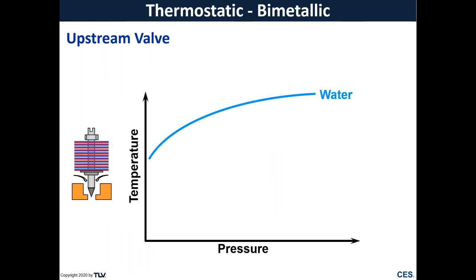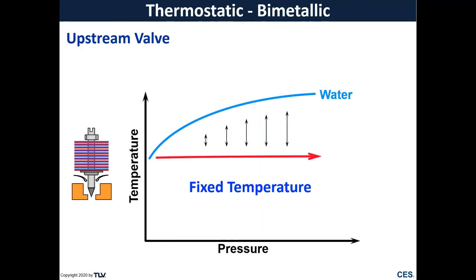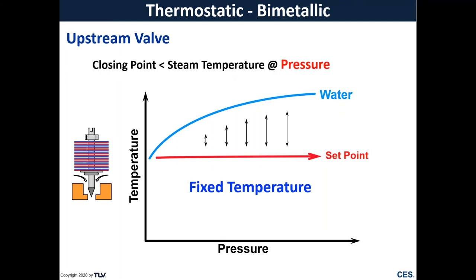So how does this look on the pressure temperature curve? Well, since this is based on temperature, we're going to have a fixed closing temperature with this upstream valve head design. And the goal here is to set this temperature lower than our steam temperature at our given steam pressure.